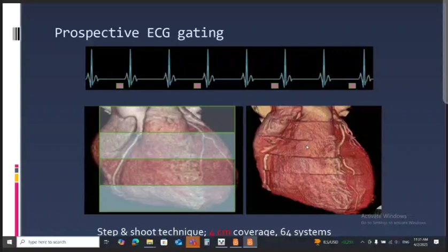It is mandatory to have a very regular heart rate, otherwise stepladder artifacts will appear between the slabs acquired. The condition is better with scanners covering 8 centimeters per rotation, like the scanners of 256 channels. And we have only one interposition line here in the middle of the heart, and we need 3 sequential cycles with extreme regularity.